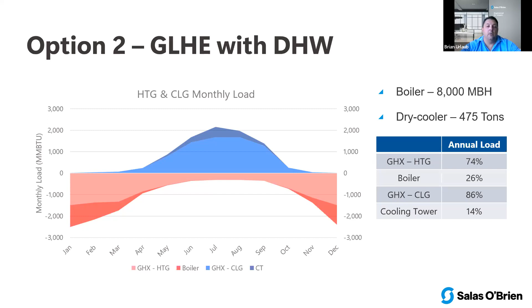Our dry cooler came down, went from a wet cooler to a dry cooler, and we cut that in half by putting the domestic hot water heat pumps into the mix, because now we're using that waste heat from spring to fall, pulling that off the condenser loop side of the building and putting that right into domestic hot water production.